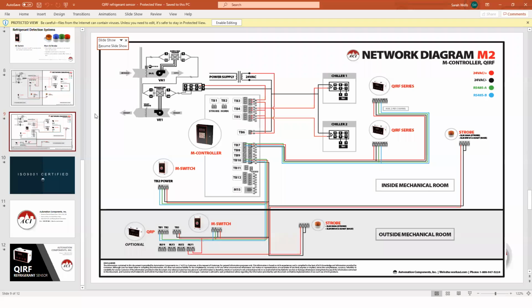So I have a question on that. All VFDs require a start signal and an analog signal. Can you do that out of the M controller or the Q controller? Can you fire a relay along with the analog? Yeah, you can do that. What I've found with the VFDs is they normally run on an analog signal. But you also need a start signal, right? Yes, yep, and that would be a relay.